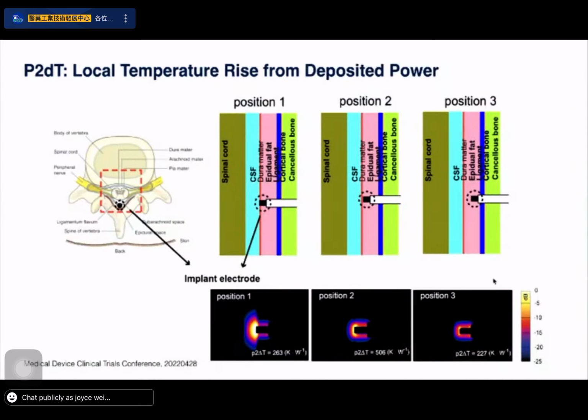Now coming to the essential parts: how do we get from the deposited power to the temperature rise and hence the risk assessment, which is what we really care about, right? To estimate if it's safe to put a patient with this implant into an MR scanner or not. This we do also with a set of numerical simulations, because we can't simply place someone in the MR and hope to measure the temperature and that it's safe for him. And the 10974 standard is mostly talking about the power deposition. But the power deposition itself in the human tissue is not what's essential to determine if it's safe or not. What's important is to know how high the temperature rise is and how long the temperature is rising.